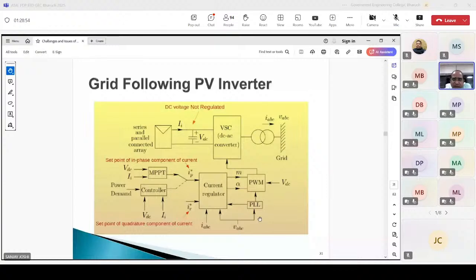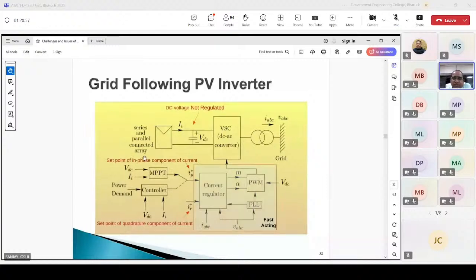This particular section of the control scheme is very fast acting. As I told you, this is the primary control loop, the shaded portion, which is relatively fast acting. This is the secondary control loop, slower than the shaded controller, and the tertiary is even further slower.